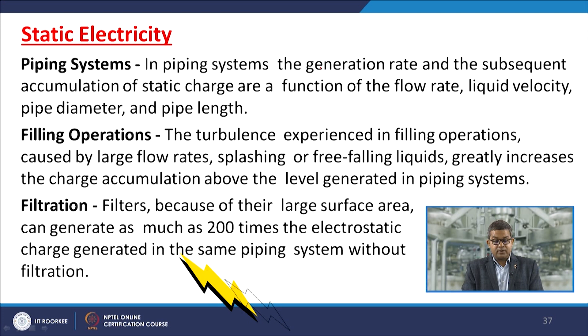Then filling operation. The turbulence experienced in the filling operation, usually caused by large flow rate, splashing, and free falling liquids, greatly increases the charge accumulation above the level generated in the piping system. We will discuss this filling operation in subsequent modules. Filtration. Filters, because of their large surface area, can generate as much as 200 times the electrostatic charge generated in the same piping system without filtration.